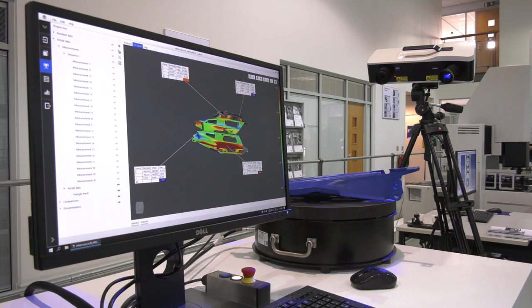And it doesn't get rid of a CMM or other machines, does it? No. What are the fundamental differences, the different areas they fit? Okay, so obviously it doesn't get rid of a CMM. A CMM is a high accuracy system. With this, you've got to reduce your resolution slightly, so you're not going to get the exact same data, but it is good for really quick measurements, capturing a point cloud and storing that on your system forever.